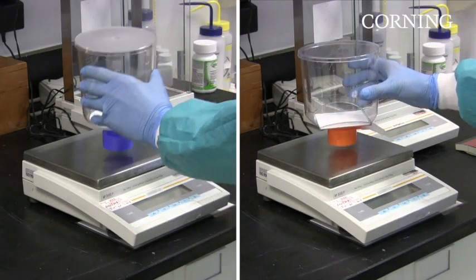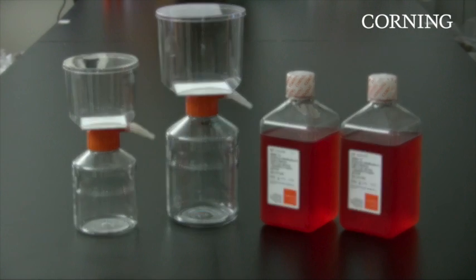To determine the hold-up volume, we first weigh both systems. From this benchmarking study, Corning's filtration system demonstrated a loss of less than 5 mL.